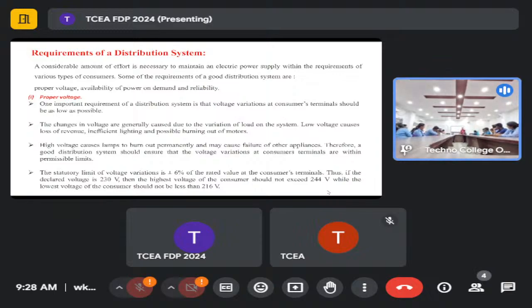And all the manufacturers of lights, fans, all domestic utilities go by the standards. Suppose 11,000 by 433. If you divide 433 by 1.732, how much does it come? Just have a look. Does it come to 250? Now 433 is the three-phase voltage, and dividing by 1.732 gives 250. Now you see, if the transformer is 11,000 by 433, that means the secondary is 250.